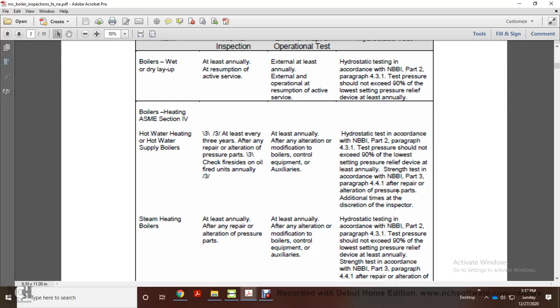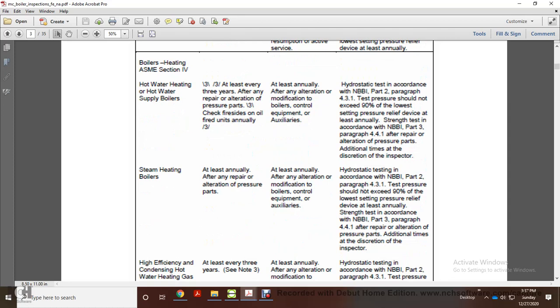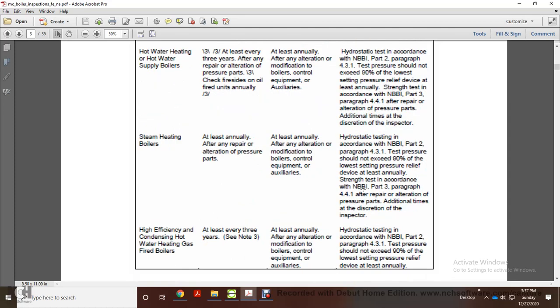After repair or alteration of pressure parts, and at additional times at the discretion of the inspector. Steam heating boilers: at least annually, and after any repair or alteration of pressure parts, and after alteration or modification of boilers, controls, equipment, or auxiliaries. Hydrostatic testing, NBBI Part 2, paragraph 431, test pressure should not exceed 90% of the lowest setting of the pressure relief device, at least annually. Strength test according to NBBI paragraph 441.